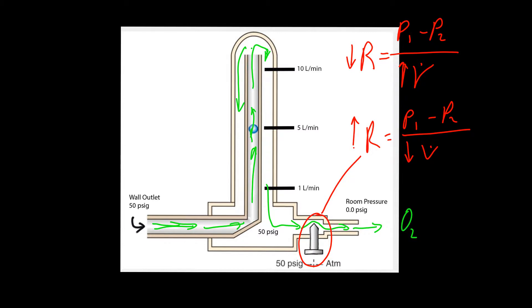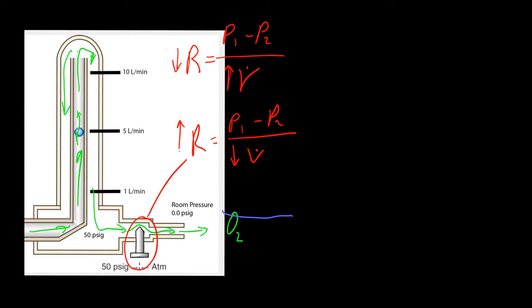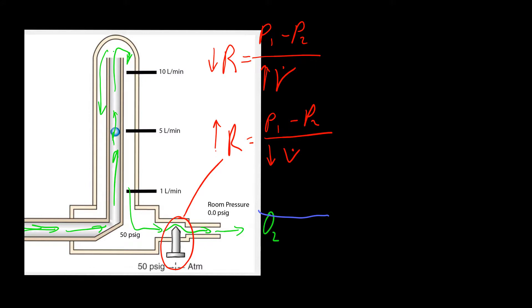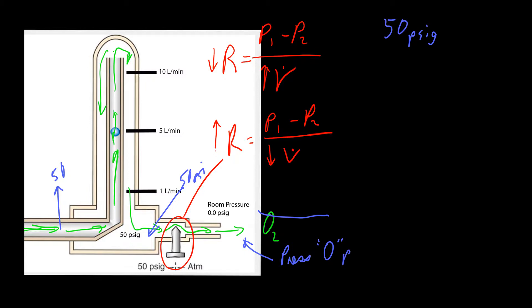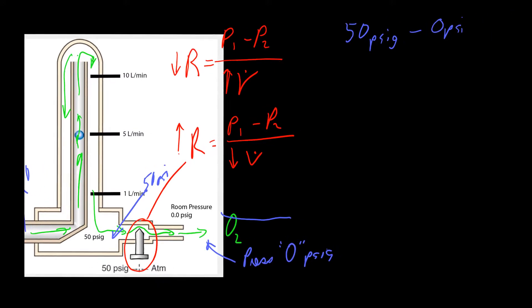The pressure gradients across the resistor are important to note because they show us what's going on with the system and allow us to make calculations. We know that on one side of the resistor we have 50 psig — that's our P1. And once the gas gets past the resistor, the pressure is effectively zero, or atmospheric pressure — zero psig. So our pressure gradient is always going to stay the same; it's always going to be 50.